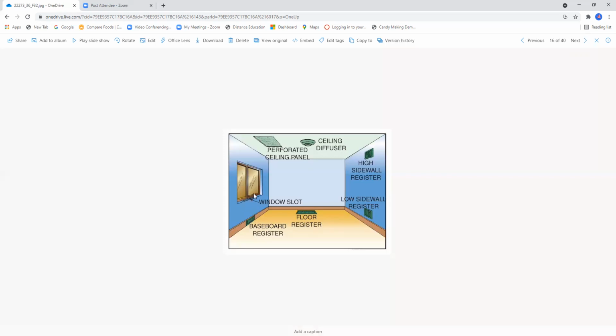And then there's the window slot. I haven't seen a window slot type thing. There's also the perforated grill. These are just different examples of how you get the supply air into a room. In order to achieve a maximum temperature exchange, I think the best thing is to have the supply air either high or in the ceiling, and then have a low sidewall return or a floor return, because basically you're forcing the heat to be drawn down here where you're at. I like returns near the floor. It works very, very well. The concept's very good. The problem is, depending on the building construction, you may be able to incorporate it or you cannot.